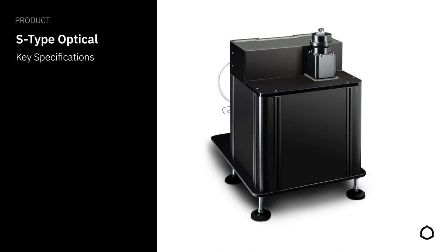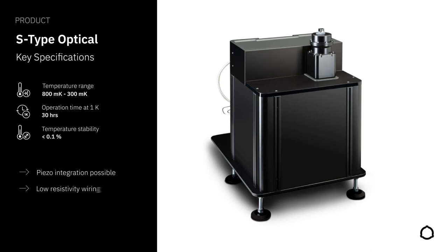In the standard configuration, the S-Type Optical features one high-capacity ADR stage for one-shot operation to 800 mK, with a hold time exceeding 30 hours at 1K. The sample stage has a diameter of 41 mm and offers enough space for a stack of piezo positioners. With our optional low-resistance wiring, the positioners can be operated over the whole temperature range, from room temperature down to below 1K. For high-frequency measurements, up to four RF lines can be added.